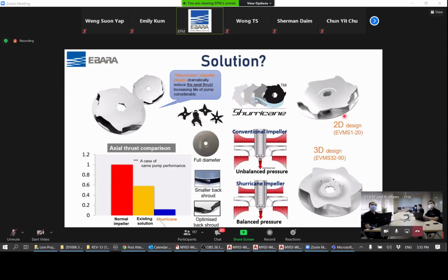And if you can see from here, what happens is that when they compare the thrust forces between a normal impeller and, in the blue one, a Shurricane impeller, you can see the difference of the axial thrust is, or rather the axial thrust is greatly reduced because of the design of this impeller. So this is one of the very good design advantages that no one has.